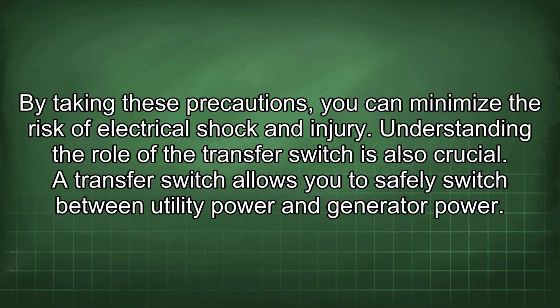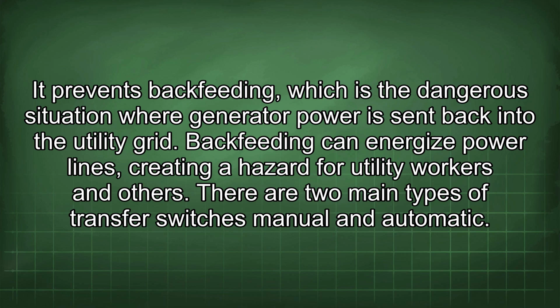Understanding the role of the transfer switch is also crucial. A transfer switch allows you to safely switch between utility power and generator power. It prevents backfeeding, which is the dangerous situation where generator power is sent back into the utility grid. Backfeeding can energize power lines, creating a hazard for utility workers and others.